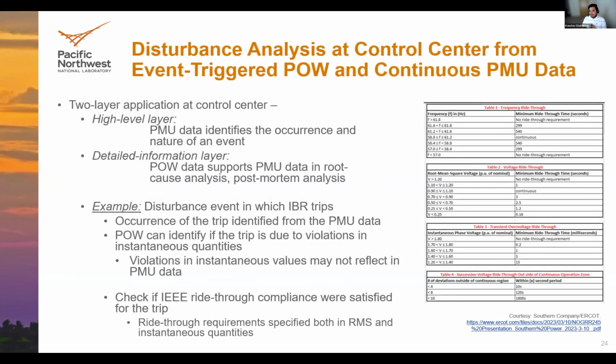So quickly, I will then move on to what we are doing with that data at the control center. Disturbance analysis at the control center, as I mentioned, will use both continuous PMU data as well as event-triggered point-on-wave data. The way we are seeing the application is that it has to have two different layers. The first layer, or the high-level layer, is using PMU data to identify the occurrence of the event and just the nature of the event. So if it's an event like an IBR trip or something, you can just see the phasor measurements of the current from the points of interconnection and say, okay, there's been a trip.